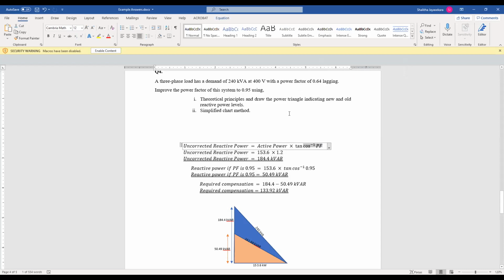So the first step of correcting the power factor is knowing the reactive power amount we have in the system. So the first step is calculating the uncorrected reactive power. You can easily do it with this equation, and for this example it will be 184 kVAR. So you can do these calculations at home and find out. And now they are asking to improve our power factor to 0.95.